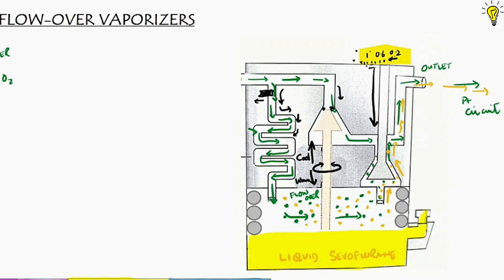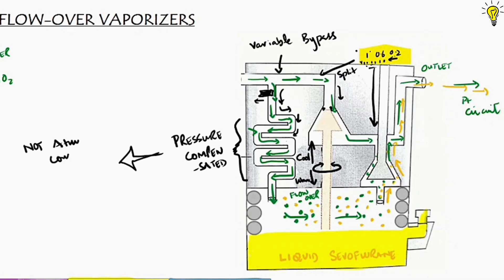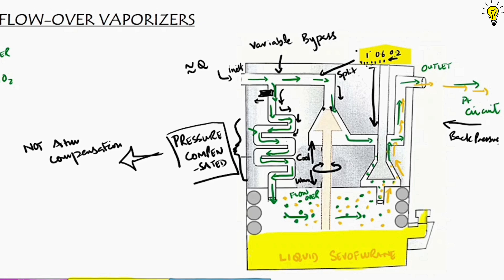Since the concentration dial and temperature bimetallic strip determine the splitting ratio at the inlet, the bypass flow changes — this is why it is called variable bypass. Second, the serpentine labyrinth serves as a pressure compensator. By pressure compensation, it doesn't mean compensating for atmospheric pressure in the ambience — a common confusion. It basically means compensating for changes in pressure at the inlet of the vaporizer and back pressures generated by the pumping effect, which may alter the vapor output.